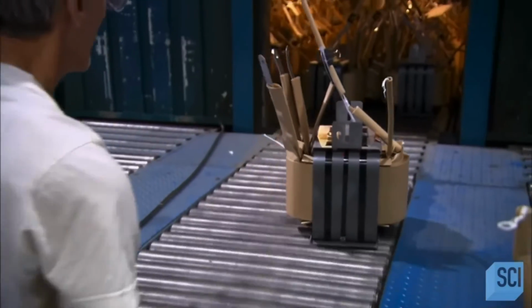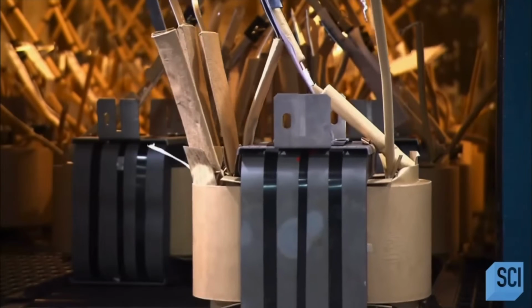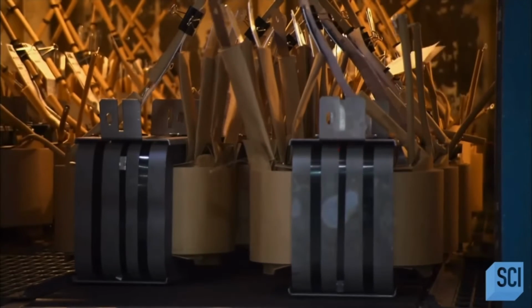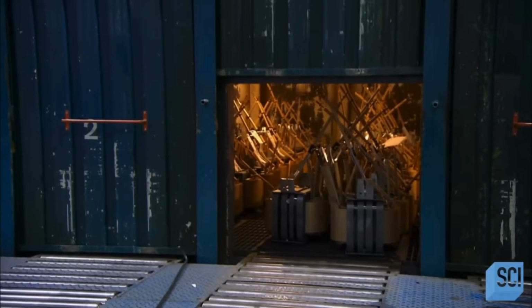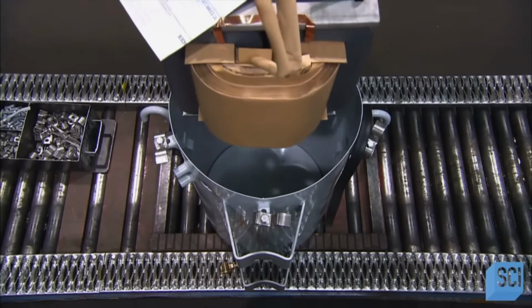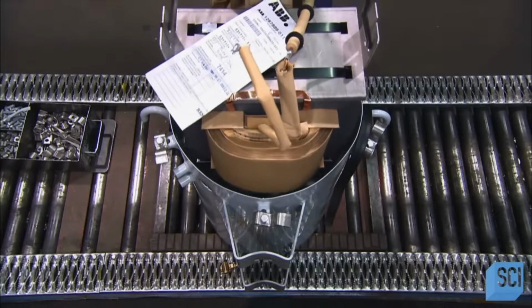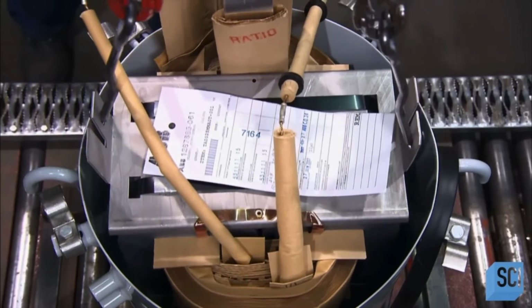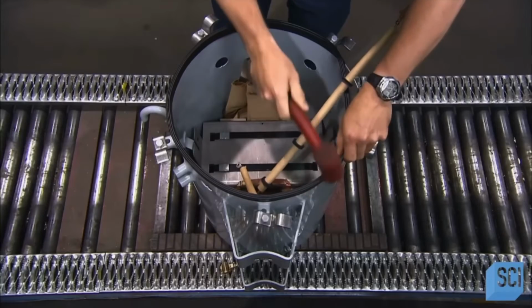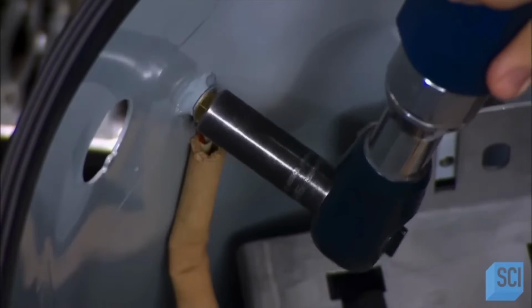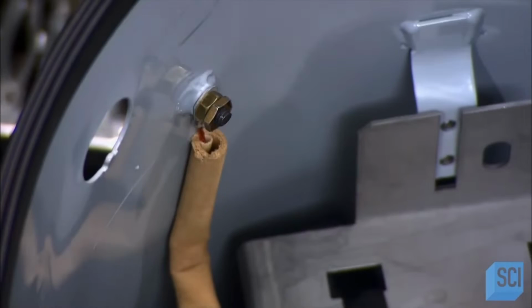Then it's into an oven, where they bake for 8 hours at 275 degrees. The heat improves insulation by removing any traces of humidity. It also melts the epoxy glue, fusing together the paper, the aluminum strip, and the copper wires. The assembly now goes into a steel tank. A rubber gasket is hammered around the perimeter, and a grounding wire is bolted on.